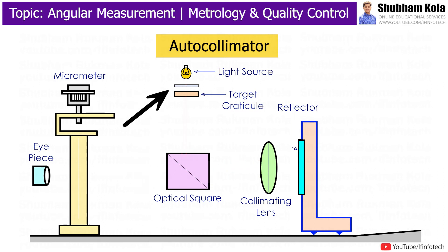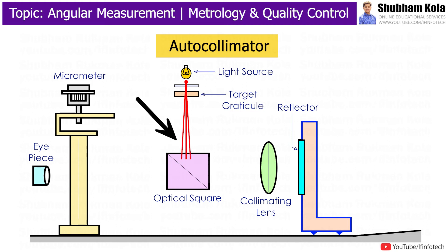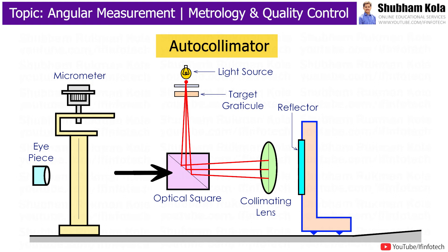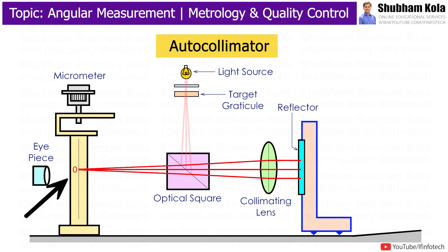During the working, when a beam of light rays comes out of the light source, the light rays are split by the target graticule and incident on the optical square. Through the optical square, the light rays change direction by 90 degrees and go to the reflector via collimating lens. If the reflector is perpendicular to the optical axis, the light rays are reflected and go in the same path, visible to the eyepiece at point O.